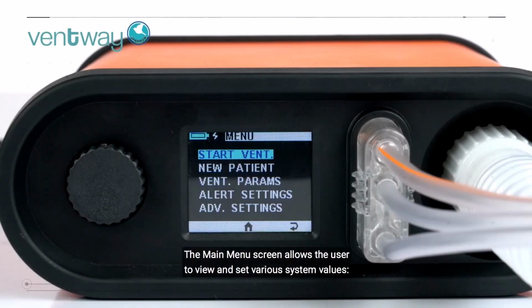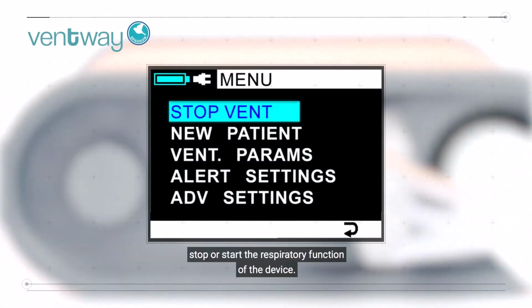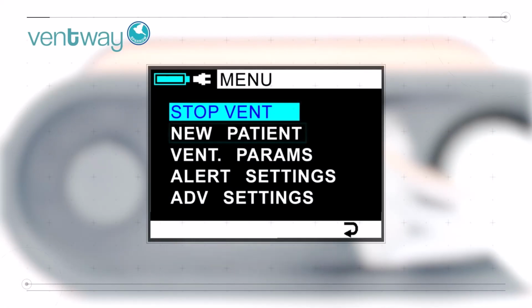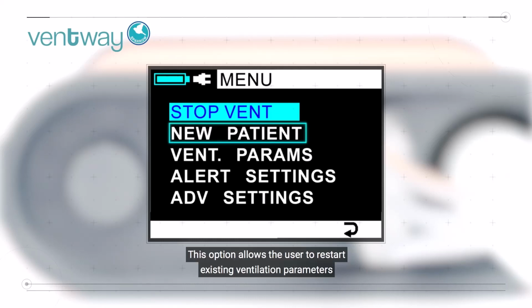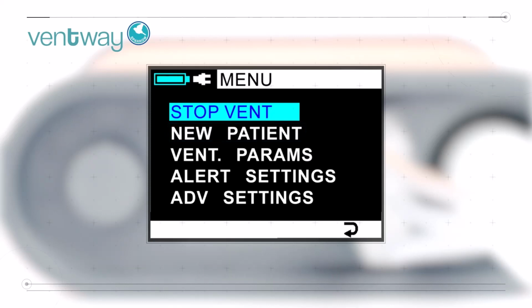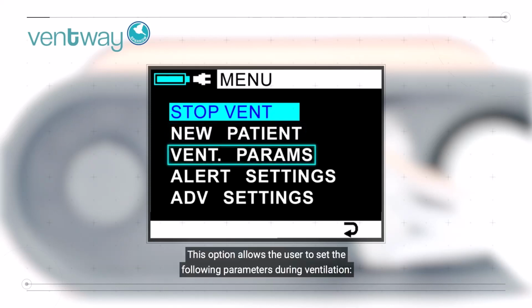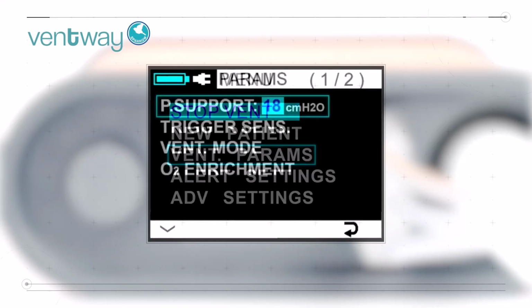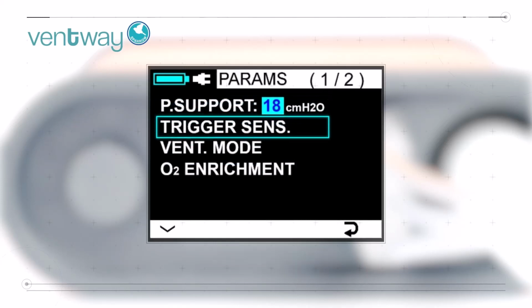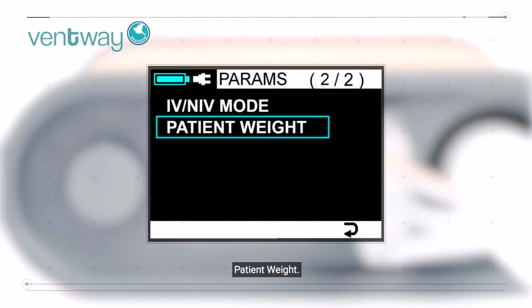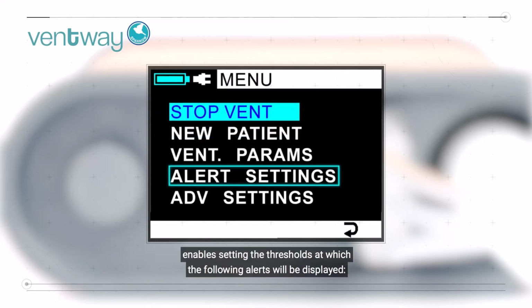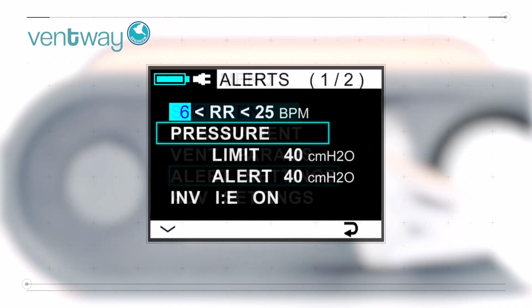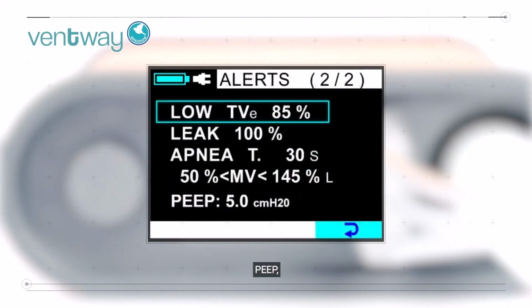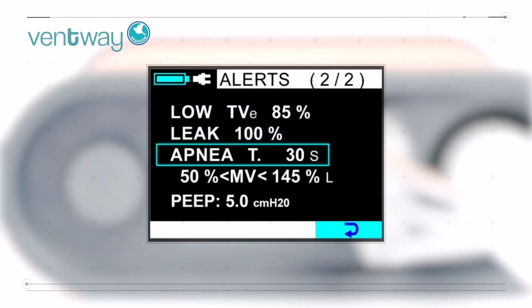Main menu. The main menu screen allows the user to view and set various system values. Stop vent, start vent: stop or start the respiratory function of the device. New patient: this option allows the user to restart existing ventilation parameters when ventilating a new patient. Ventilation parameters: this option allows the user to set the following parameters during ventilation: pressure support level, trigger sensitivity level, ventilation mode, FiO2 level, invasive or non-invasive ventilation, patient weight. Alert settings enables setting the thresholds at which the following alerts will be displayed: pressure, IE ratio, PEEP, low or high tidal volume, leak, apnea.